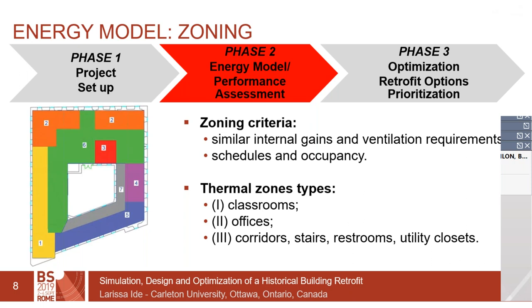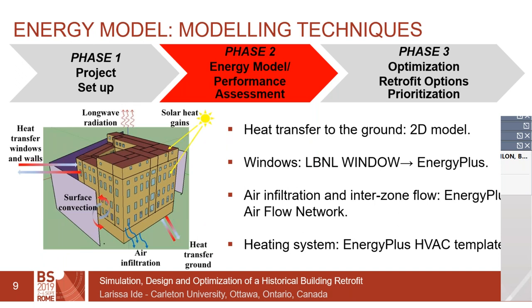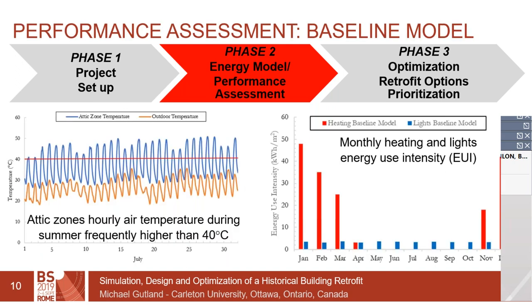This resulted in about seven zones per floor. We further divided zone types by orientation, which is why there are many zones — corridors were also split by orientation to accurately model natural ventilation. Our modeling techniques included 2D heat transfer to the ground, LBNL Window to input window frame and glazing properties into EnergyPlus using the complex fenestration model, an airflow network for air infiltration around windows and interzone airflow, and HVAC templates in EnergyPlus to model the heating system.